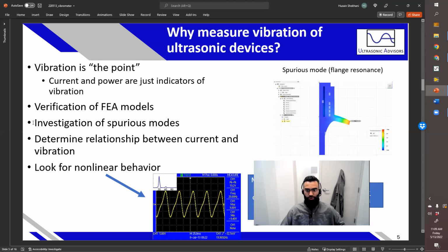A lot of times these spurious modes are not very well electromechanically coupled. However, they can provide a lot of detrimental results for your specific transducer. They can take away energy from the main mode. They can also cause failure. For example, some ultrasonic transducers have electrode tabs sticking out to power the piezo ceramics. Those tabs can undergo oscillations which are not detected very well using impedance, but are detected very easily using a vibrometer, basically a displacement or ultrasonic transducer mechanical measurement.